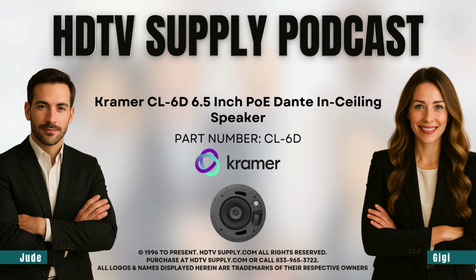That is brilliant. And when you do get up there, the installation looks pretty painless. It uses a dog-ear clamp system for ceilings up to 2.36 inches thick. Standard for drop ceilings, yeah. Right, but it features front access wiring, so you don't even have to crawl up into the ceiling to adjust the connections. Which is great because you really don't want to be messing around in the plenum space. That area above the ceiling is used for air return, so safety is highly regulated. You can't just shove a standard plastic box up there. No, it's a massive fire hazard.